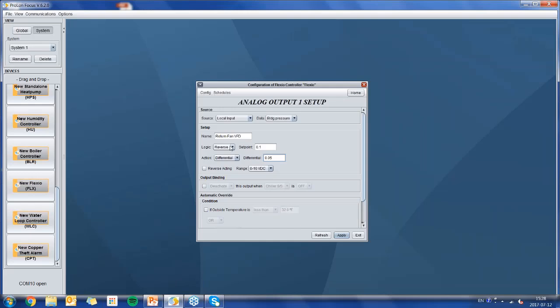We want to make sure that it's reverse acting, and we want to make sure it is not differential, it's not on-off, but we actually have a proportional integral, because it is a modulating signal. And supply, there we go. That's all we need. Here you can choose the range for our voltage range for the VFD.